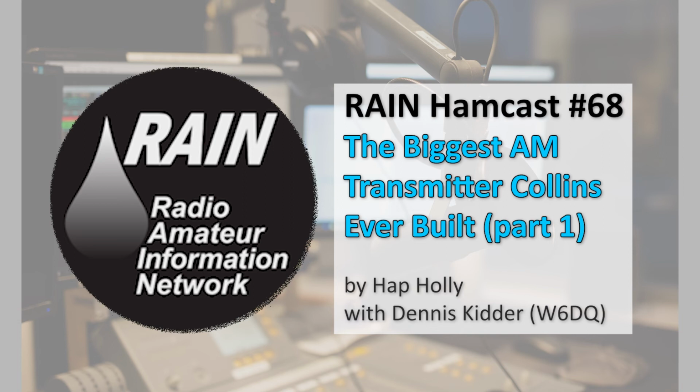Each transmitter, and there are 3 of them at the site, each transmitter uses 4 CV 100,000C vapor phase cooled tetrodes. This is a 100,000 watt vapor phase cooled tube, meaning that tube sits in a pot of water, and when it gets hot, the water boils, the steam goes off to a condenser, which is located up on the second floor of the building, is returned back down as cooled water, and continues the cycle. Each of those tubes runs at 17,500 volts at 15 amps. Oh, that's a lot of power.